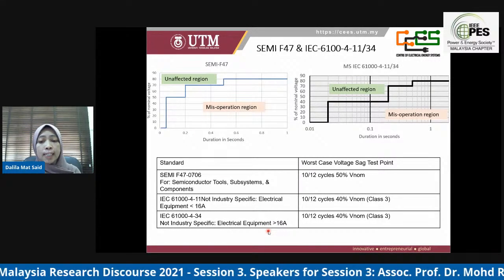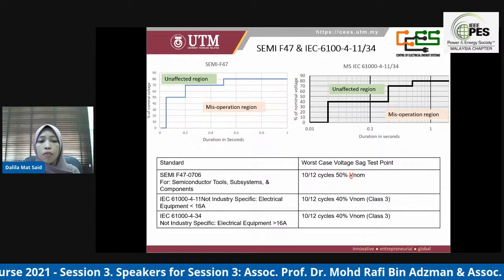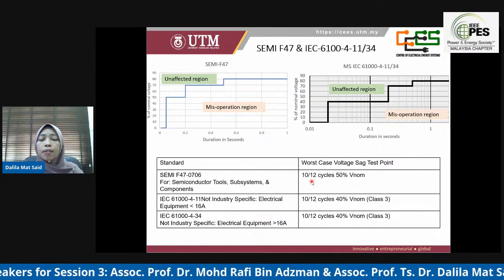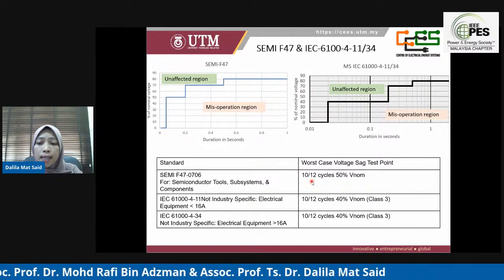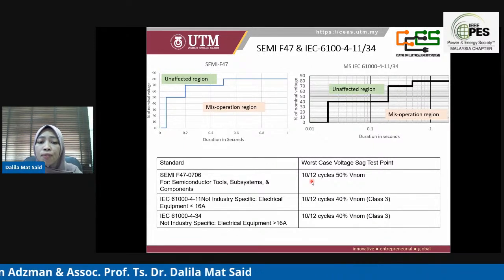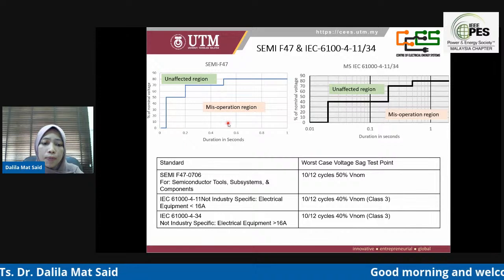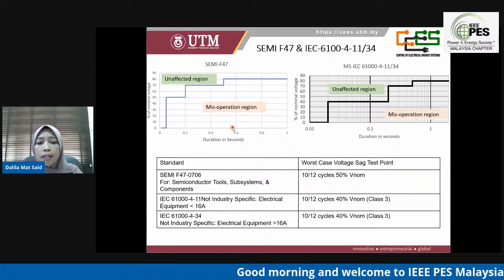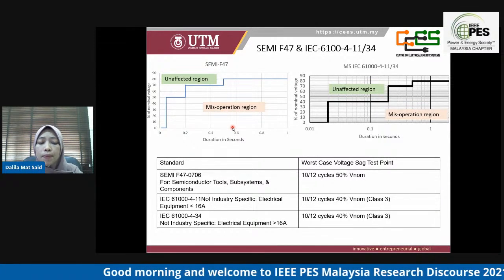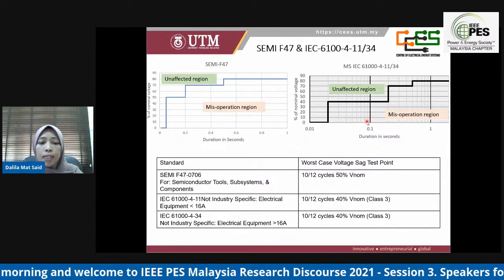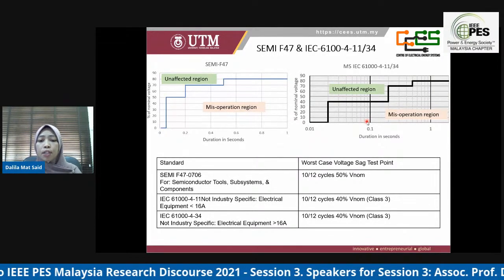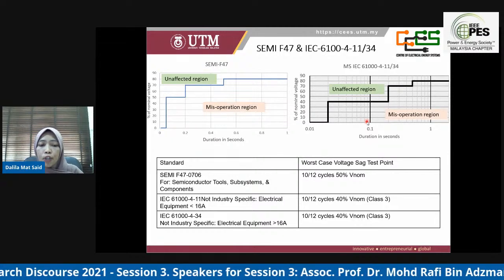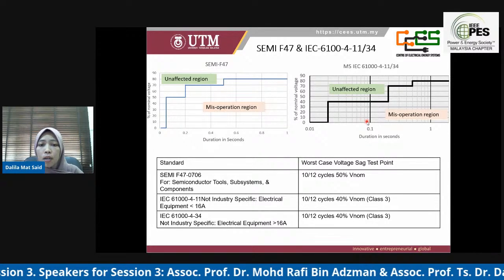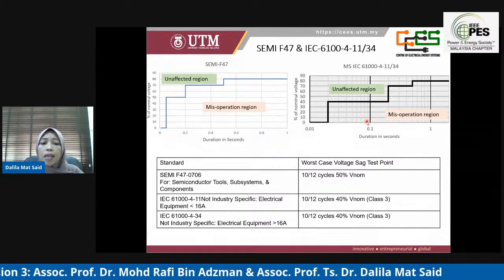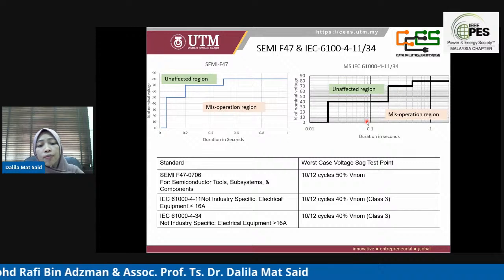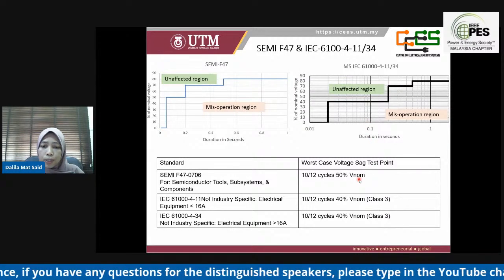SEMI F47 is an industrial standard for voltage sag immunity. It states that industrial equipment must tolerate voltage sags in the AC mains supply to a specific depth and duration, as you can see from the curve. It is a useful standard, and many other industries use it, either formally or informally. And the IEC defines the immunity test method and range of preferred test levels for electrical and electronic equipment connected to low voltage power supply networks for voltage dips, short interruptions, and voltage variations. The standards have different test levels and also durations.